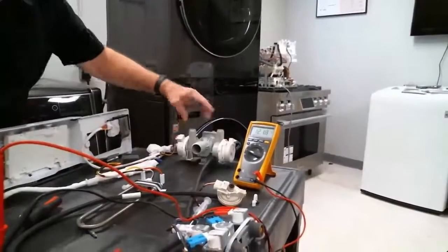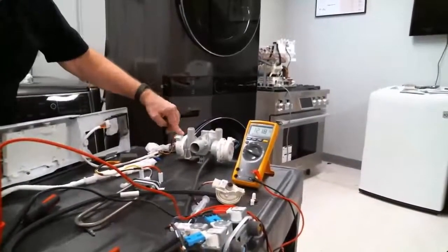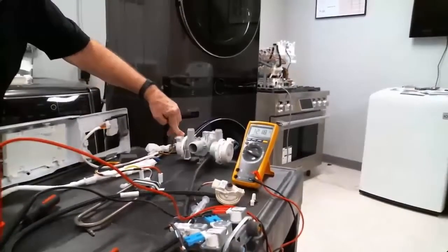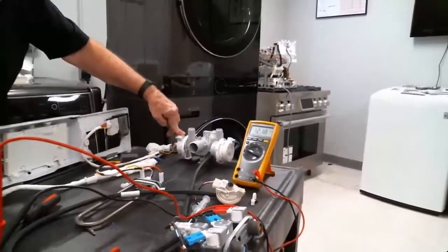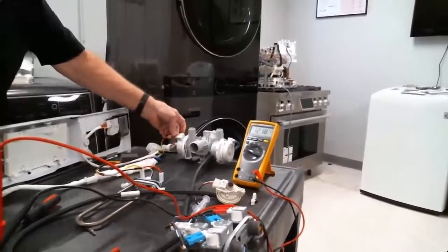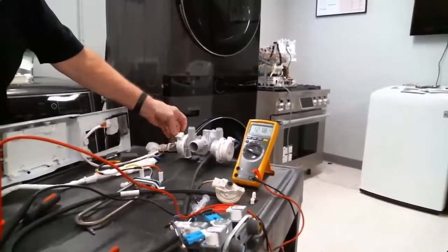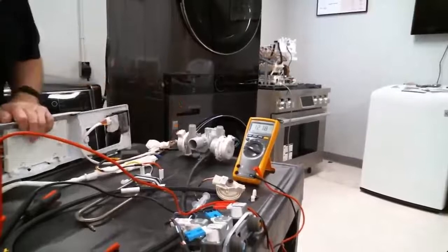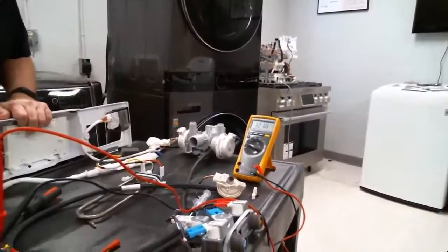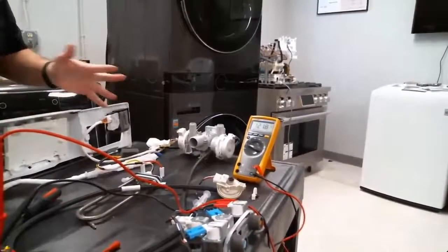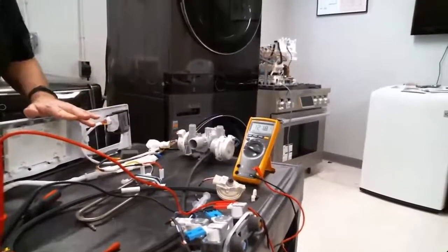What I normally see in those situations is a lot of shorted drain pumps. So that's really easy to check. We can check right at the main board to see if we've got a dead short on the drain pump. Go ahead and replace that, and then also replace your main board. So it's real easy to check that circuit inside there.